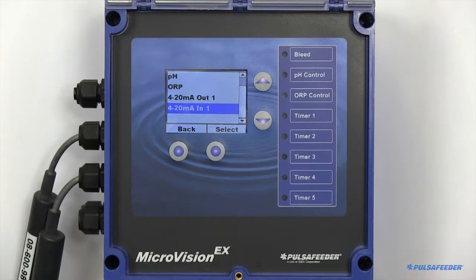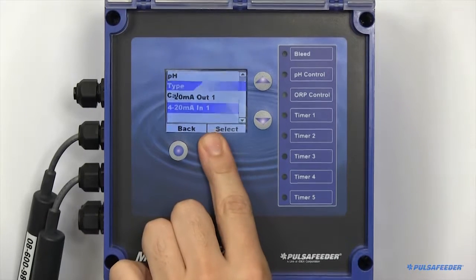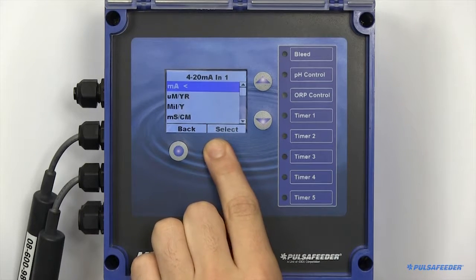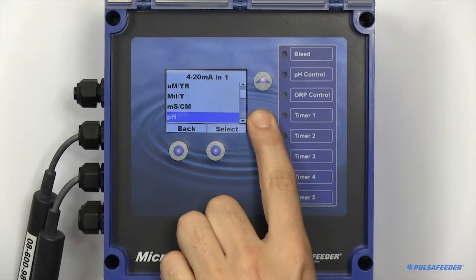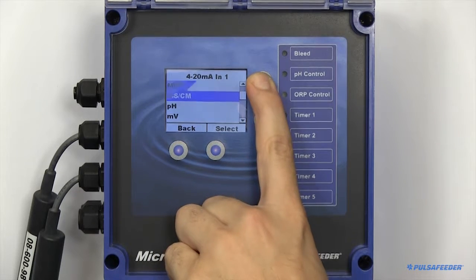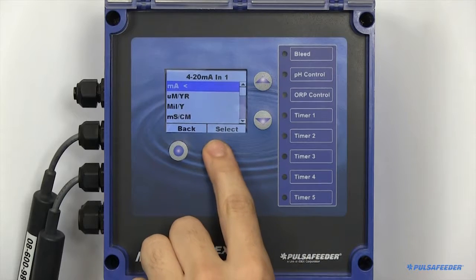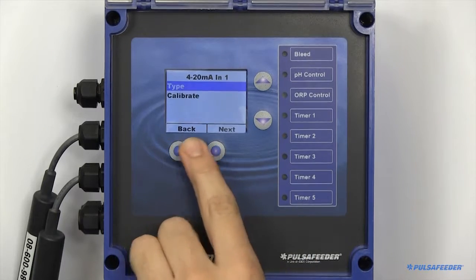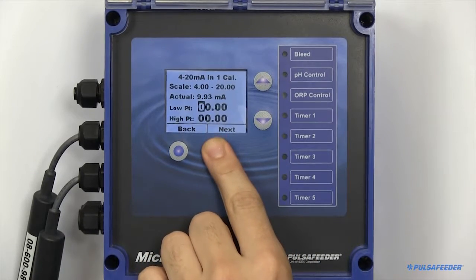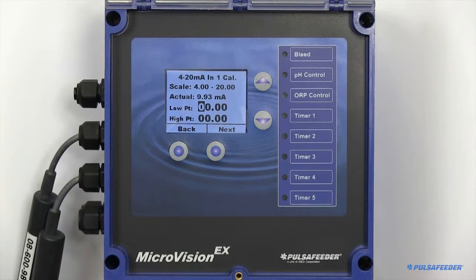Four to 20 input boards can also be configured. It's very similar to configuring your 4 to 20 output. First, you must specify the type. After specifying your type, you then need to calibrate the board. You may need buffer solutions to perform this. The top row indicates your low point. The bottom row is the high point. You will need two buffer solutions.